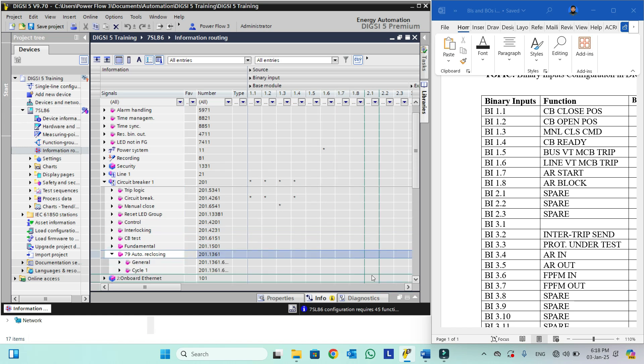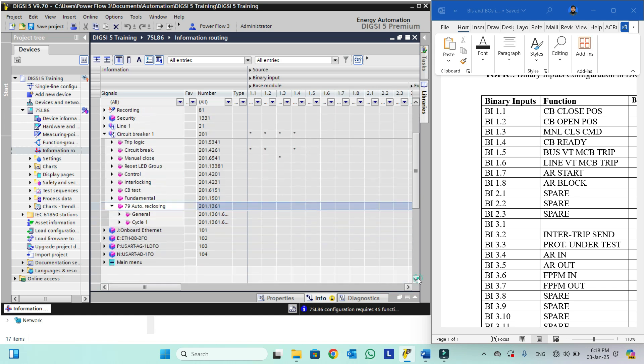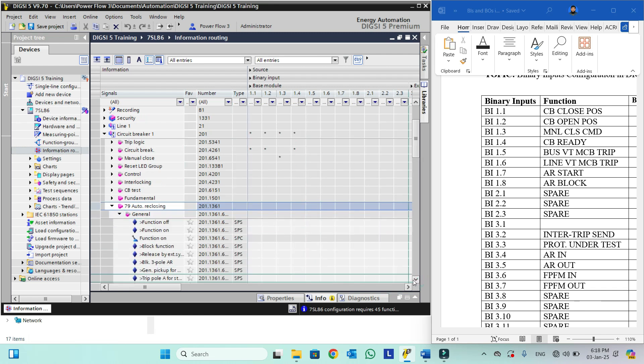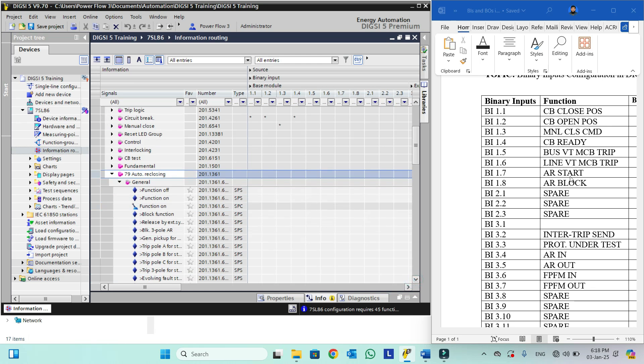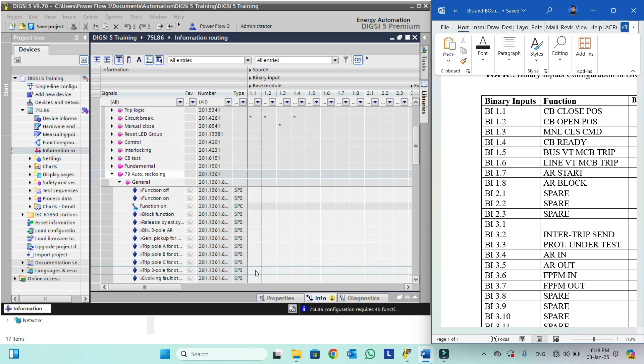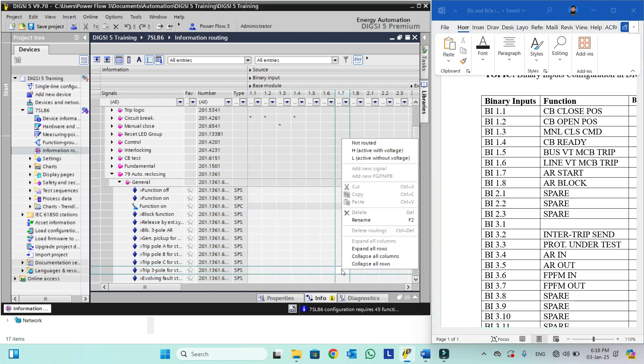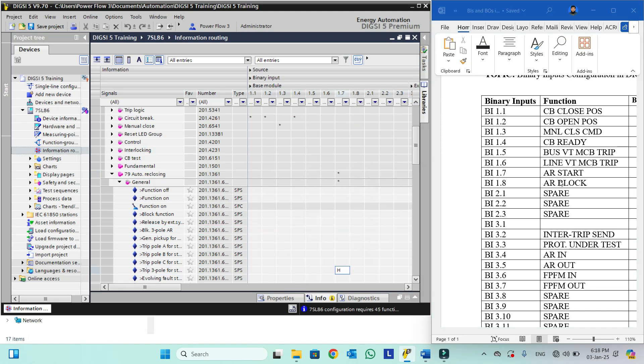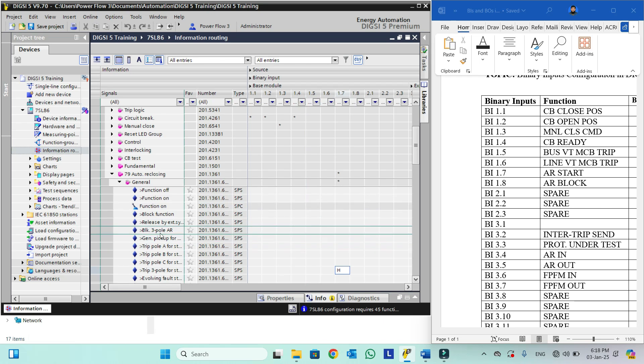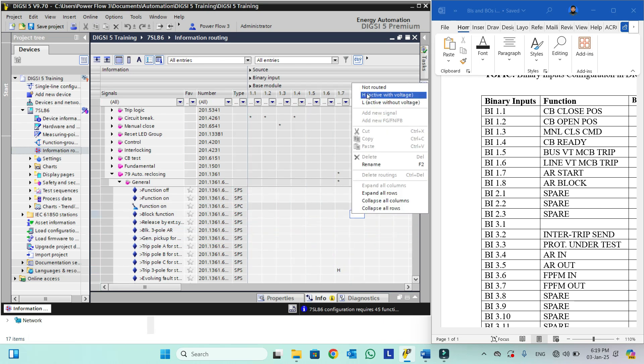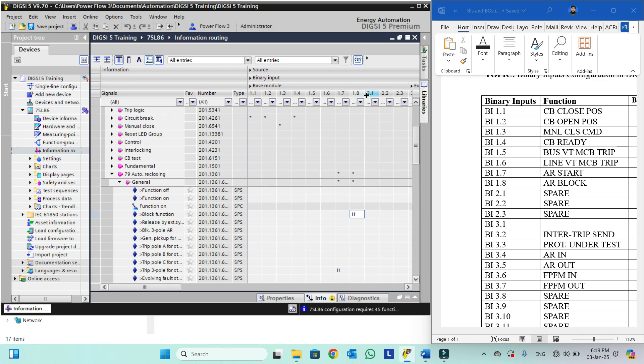We will go here and configure this binary input. This is actually the external AR start, so for external AR start we can select binary input trip 3-pole for start. This is number 1.7, active with voltage. We also have AR block 1.8, so we can configure block 3-pole AR. This block function I will configure as 1.8.